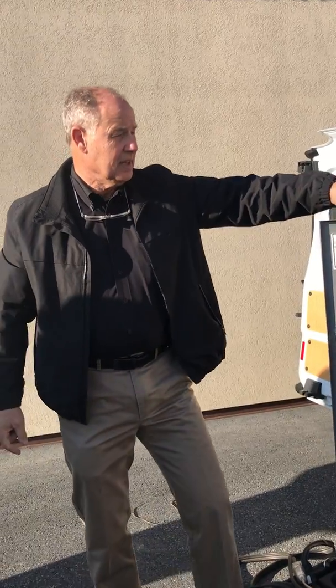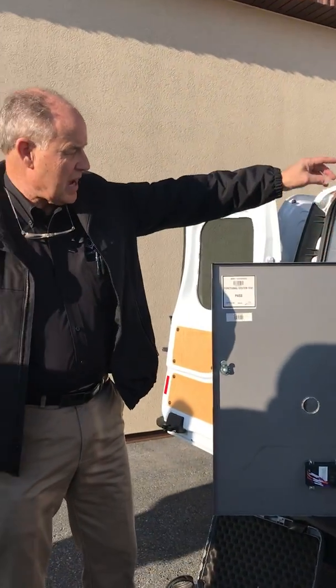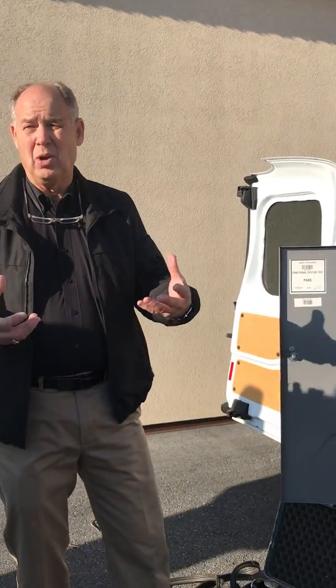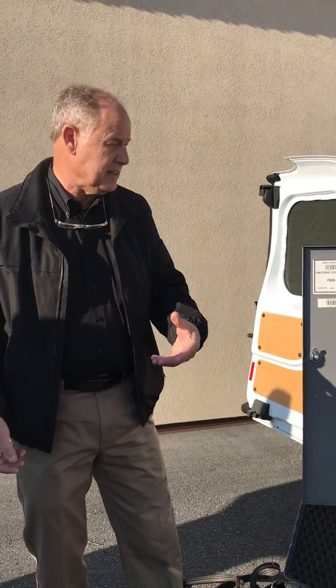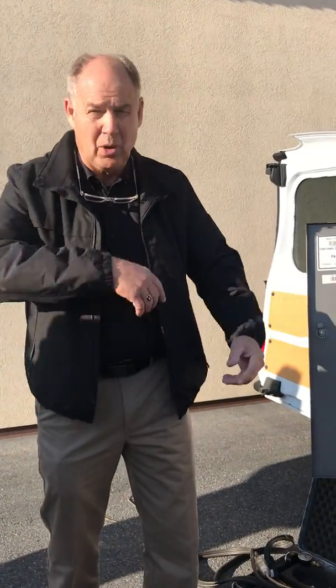That's doing one thing. The other thing it's doing is we actually look at if cold air is coming in, we're actually looking at the boiler if it gets too cold inside. Well, actually that's not the stack, the supply is actually doing that. The supply sensor is actually looking at the temperature in the boiler, and if it gets too cold, we actually turn the pump on and start circulating water so we don't freeze. You gotta realize these go out in Wisconsin, Chicago. You can get cold air coming in, you get a short vent, cold air comes, we can freeze our heat exchanger.